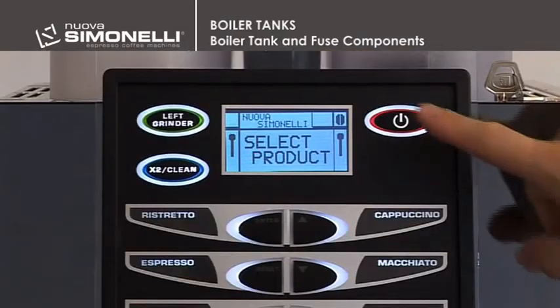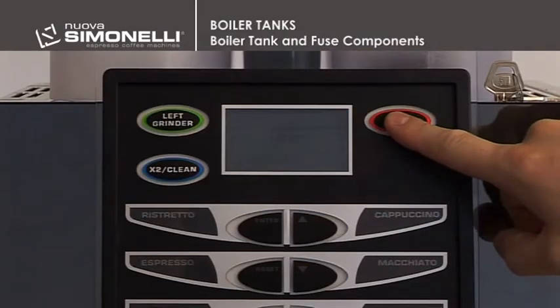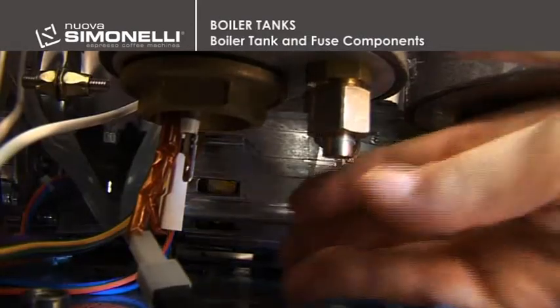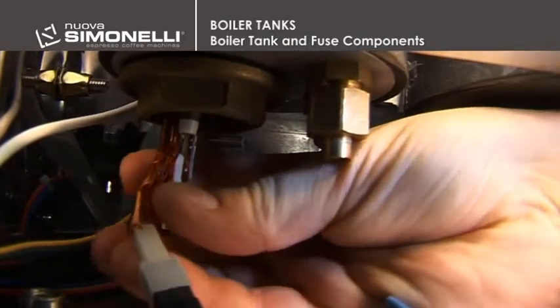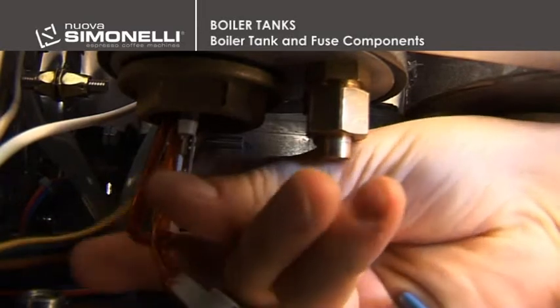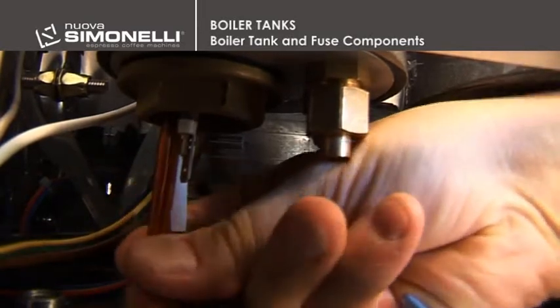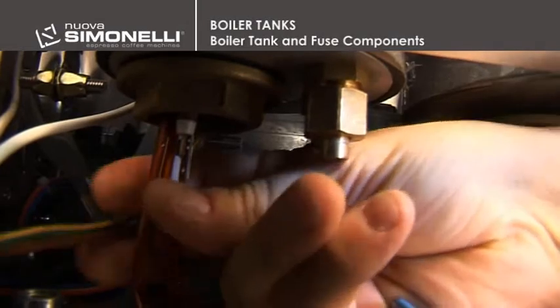To replace the fuse, it's necessary to switch off and unplug the Talento. Next, disconnect the fuse connections and slide out the fuse from the bottom. This operation takes place in the bottom part of the boiler tank.